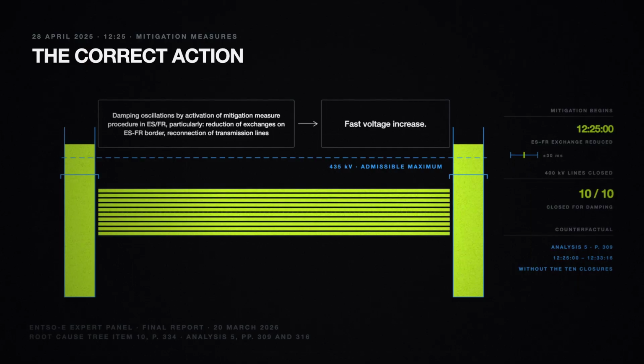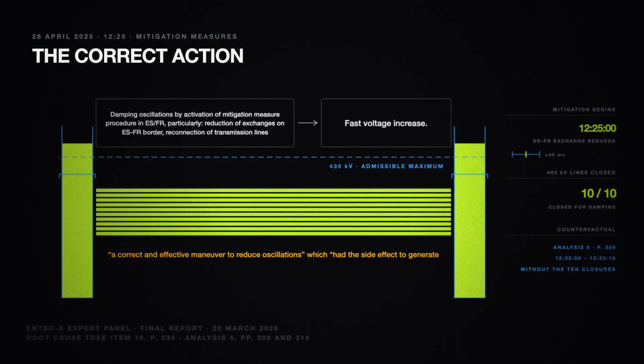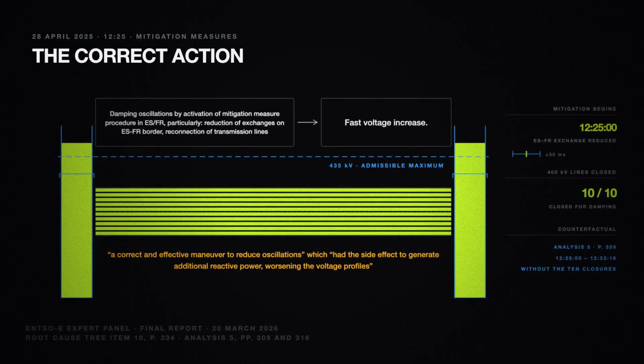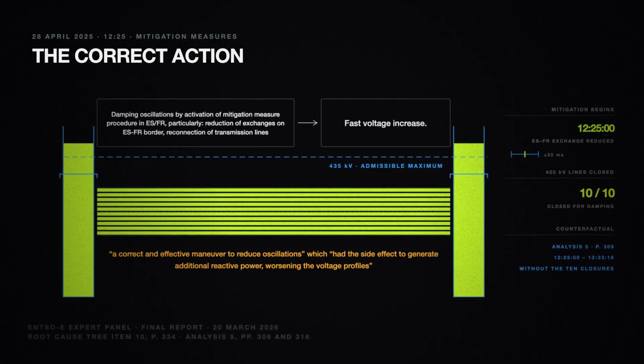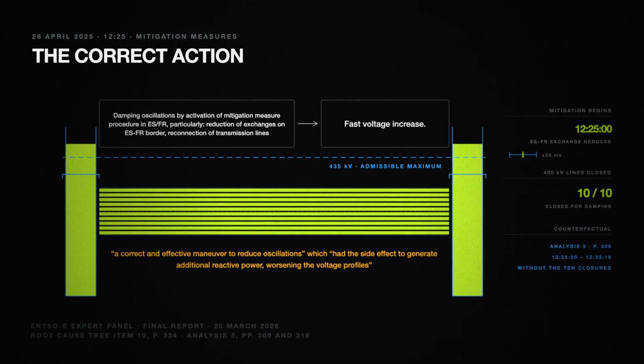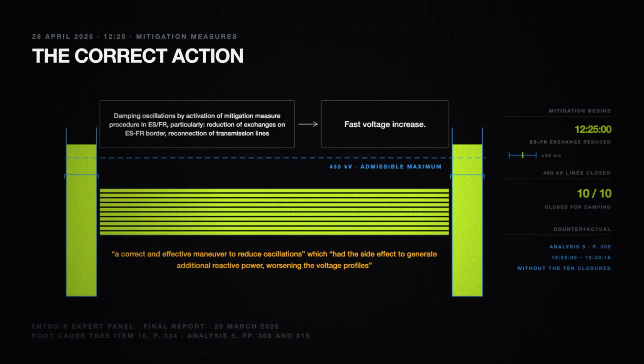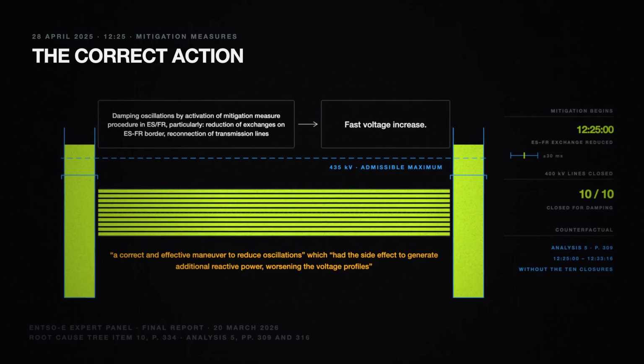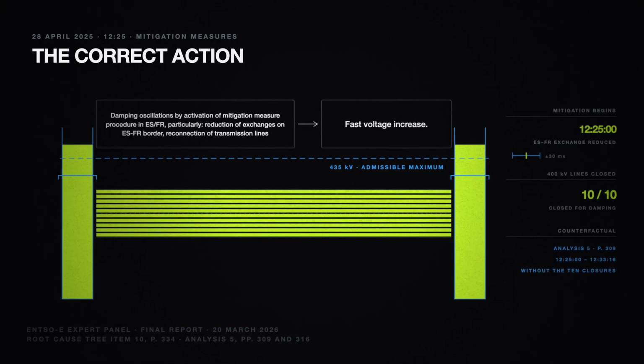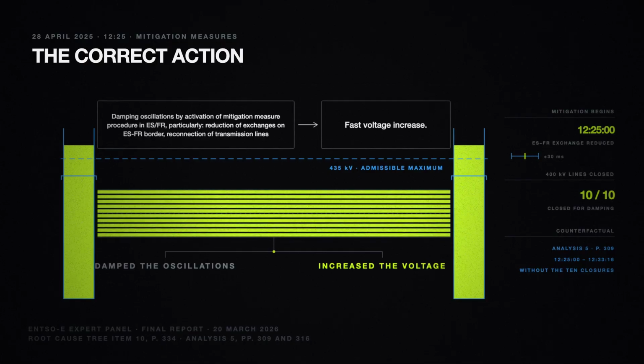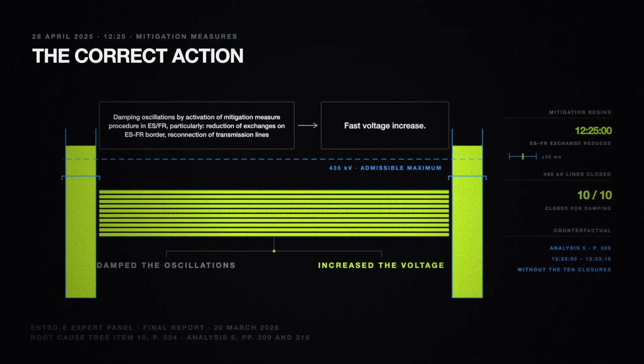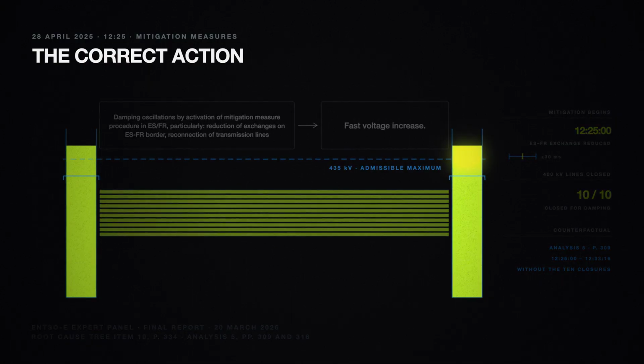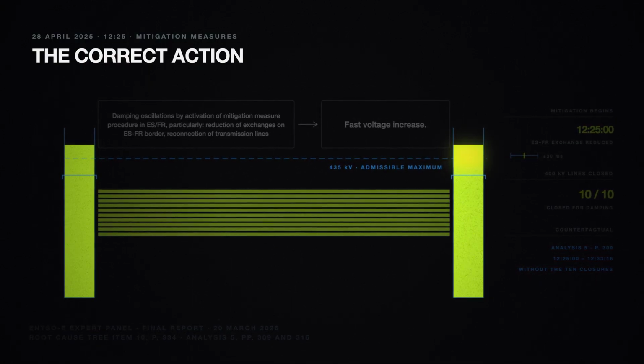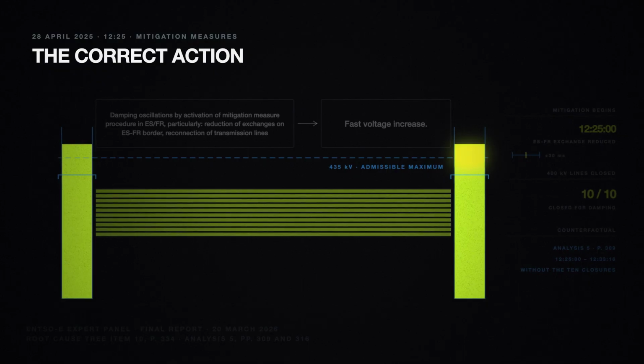The same page again on reclosing transmission lines. A correct and effective maneuver to reduce oscillations, which had the side effect to generate additional reactive power, worsening the voltage profiles. 1 action, 2 consequences, and the report does not separate them into a good half and a bad half. The panel does not blame the operators, and this is why. Nothing here was a mistake.